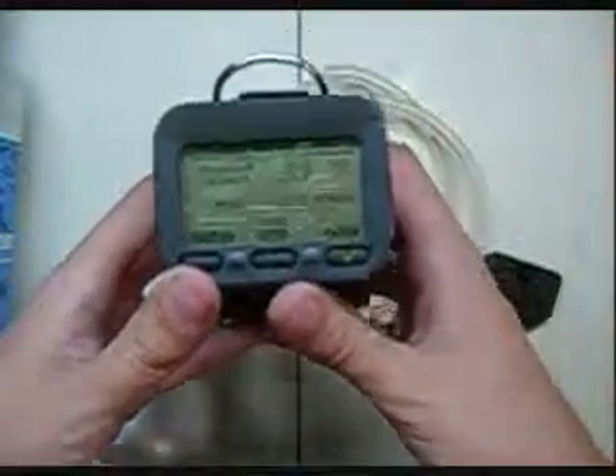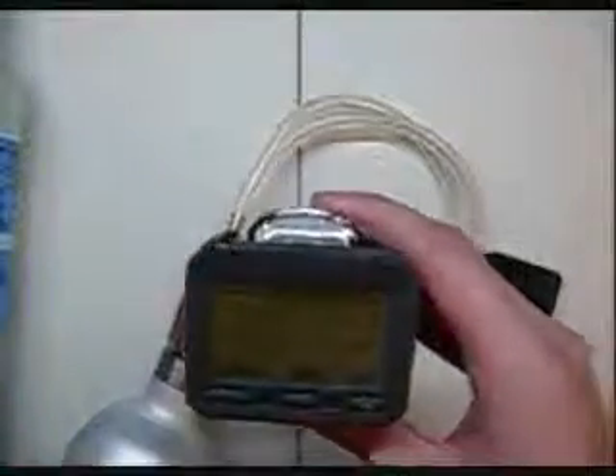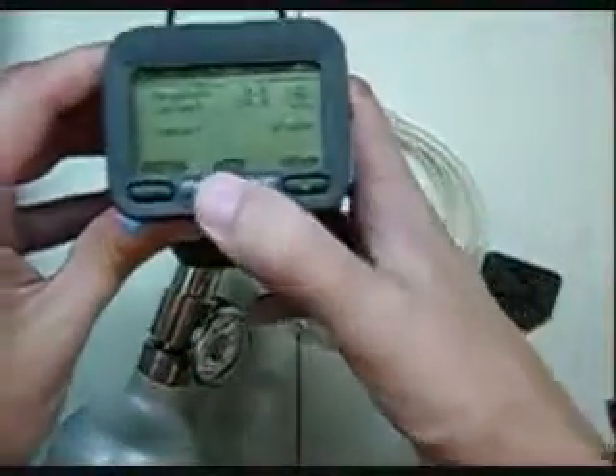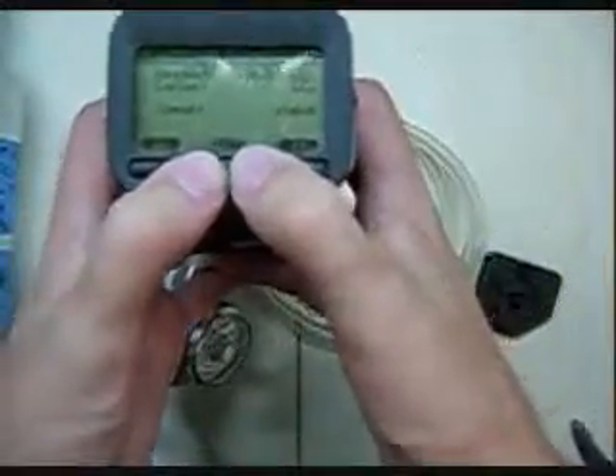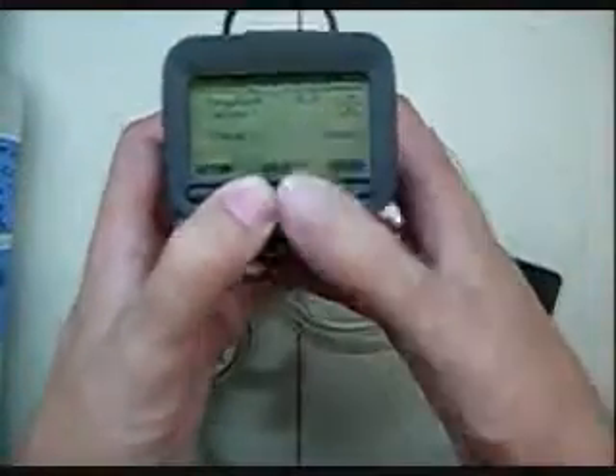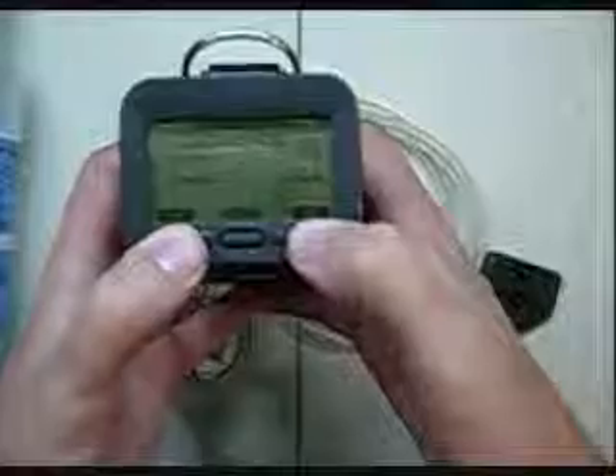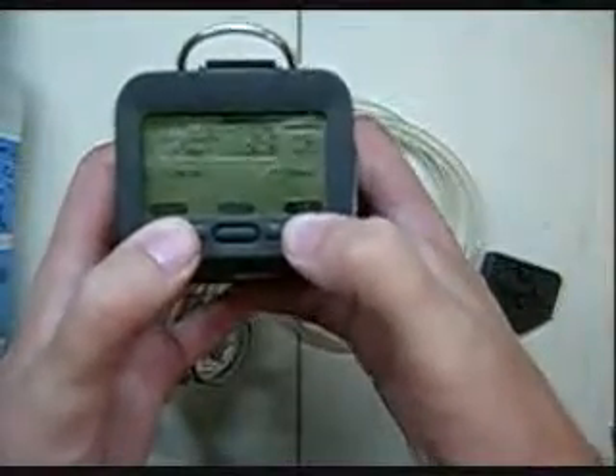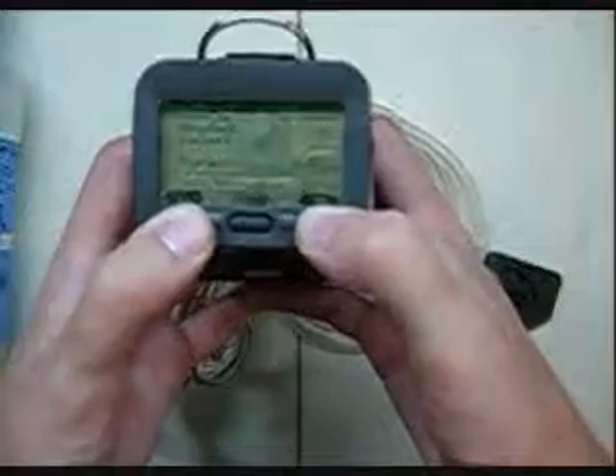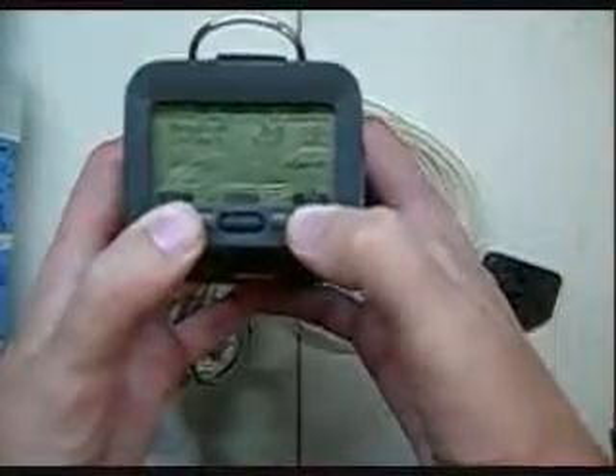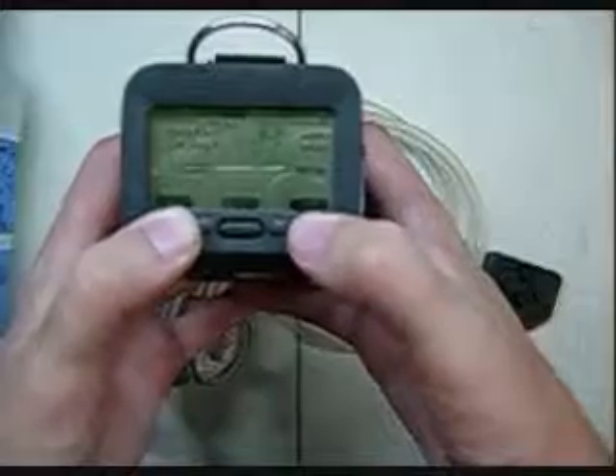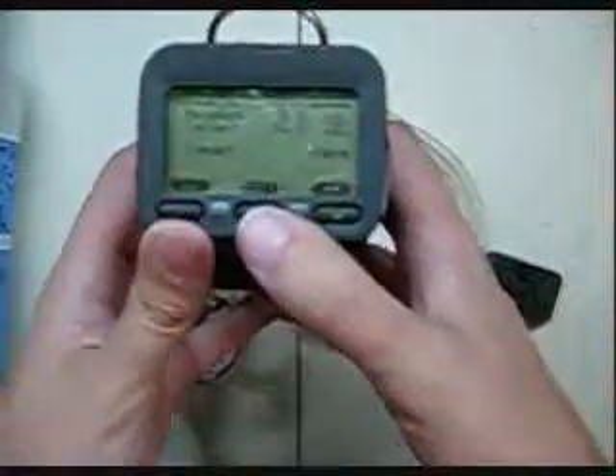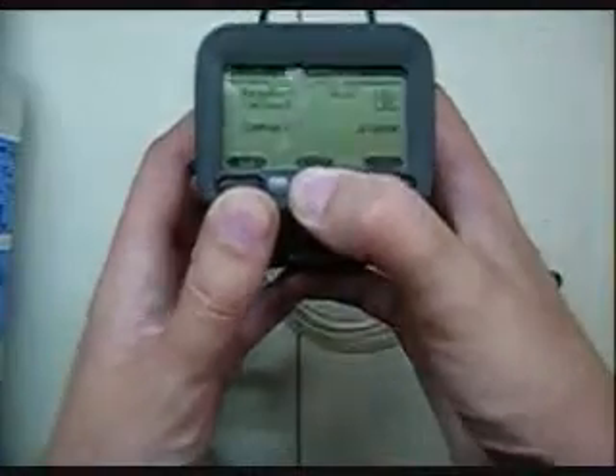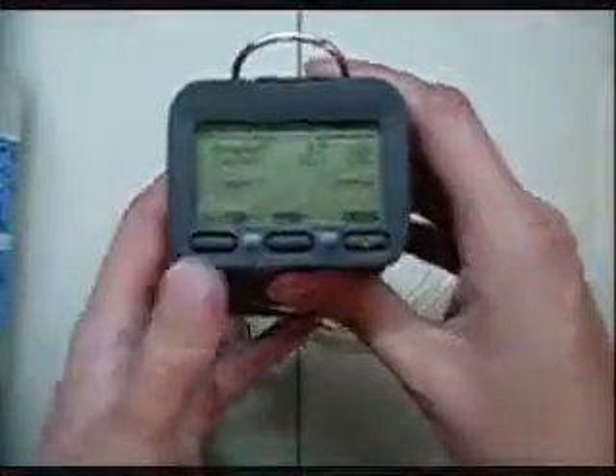Press select, go down to calibrate, and it'll bring up a readout screen. The first thing to look at here is that I have this one set up for 29% LEL, and actually it's going to be 50% LEL. I'll show you how to change it. Press the middle button. This number here will begin blinking. Hold up till you get to the value that you want. In this case, I'll be using 50% LEL. Once we have the correct value, we hit exit, and now we're back at the gas screen.